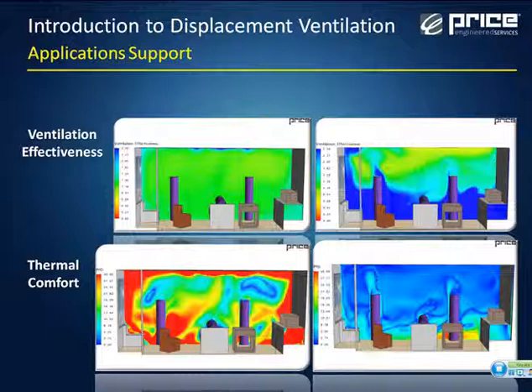But the rest of the room is pretty well fully mixed, so we see the contaminants even throughout the room, which is not great if this person in the bed happens to have a compromised immune system, or someone else in the room is sick, or this person in the bed has something contagious that they don't want to be passing to other people in the room. Basically, that mixing diffuser in the ceiling is mixing everything around the room. So everything that one person is breathing, the other 2 people in the room are breathing as well.